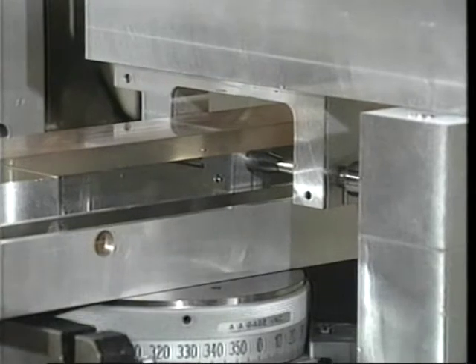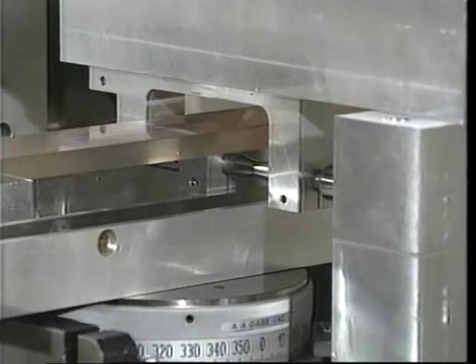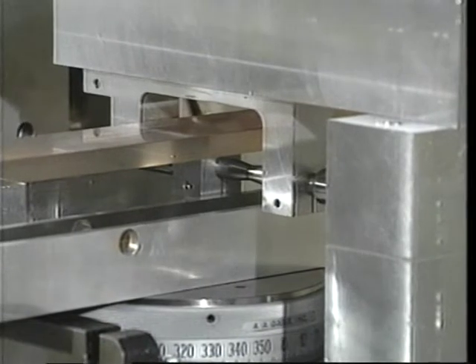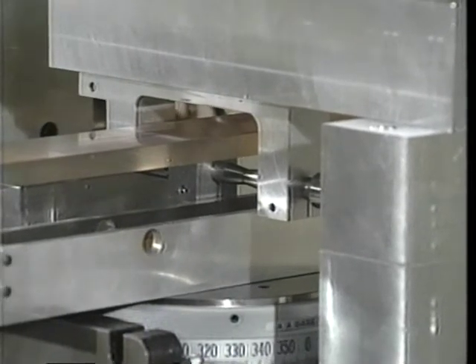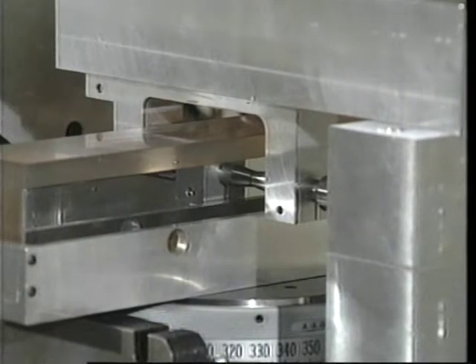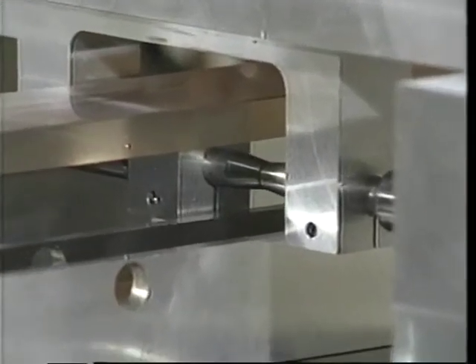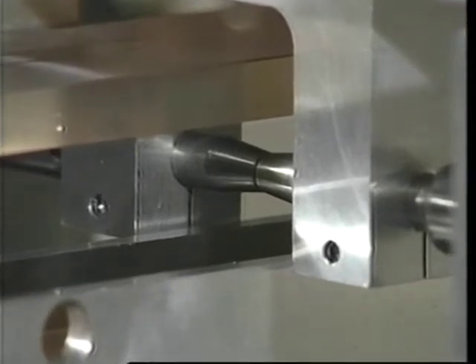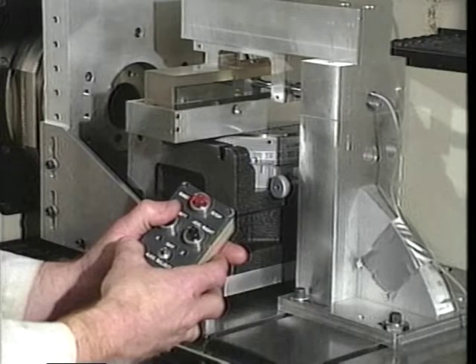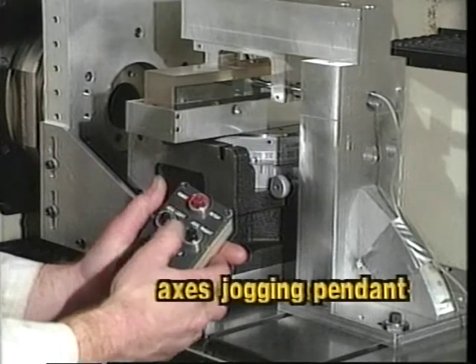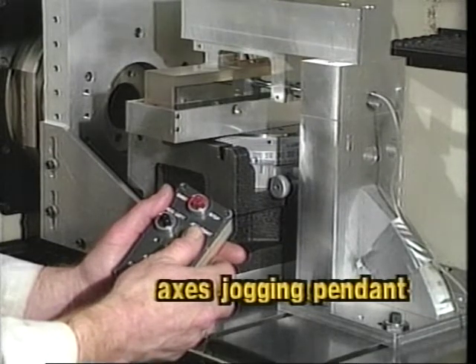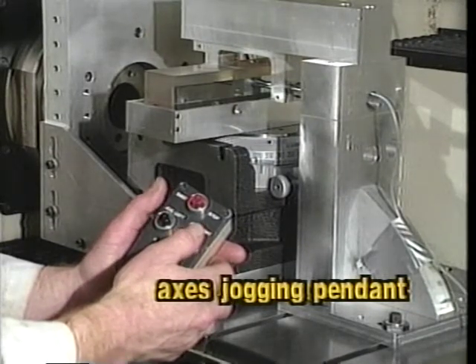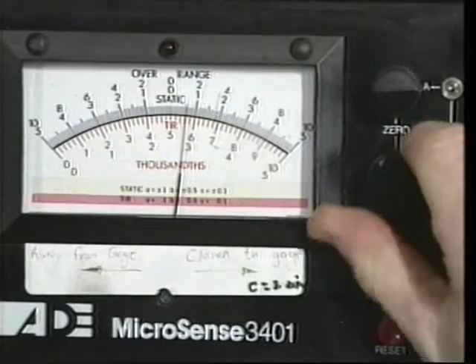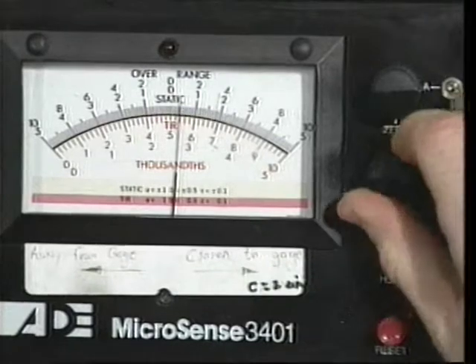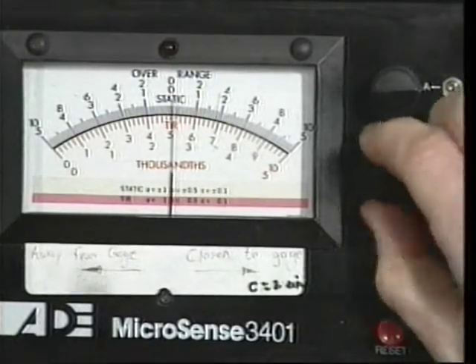Before measurement can begin, the straight edge must be brought to an orientation which is parallel to the x-axis of motion. To begin this procedure, the x-axis slide is moved until the cap gauge probe is approximately positioned at the center of the precision index. The separation of the cap gauge probe and the straight edge is adjusted until the console reading is within the plus or minus 0.001 inch range of the cap gauge. Using a combination of physical positioning and electronic zeroing, the meter needle is brought to mid-range position.